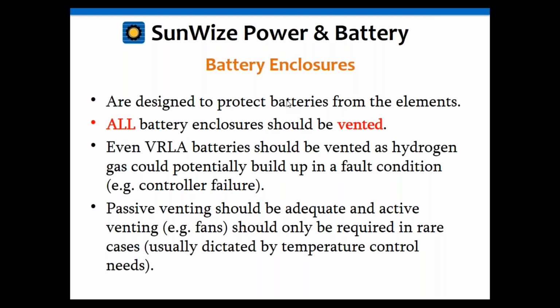I'm going to talk about, if you do need a sealed NEMA 4X enclosure, how do you handle that situation? I'll talk about that a little later when we discuss battery enclosures and how to do that. But keep in mind, all enclosures must be vented, there has to be some type of ventilation. There are also many standards on that. You can look at the NEC, but IEEE has several documents with regards to battery enclosures, and they all talk about how they have to be vented in some way, shape, or form. Battery rooms all have to be vented too, so they talk about that. You always have to have ventilation.